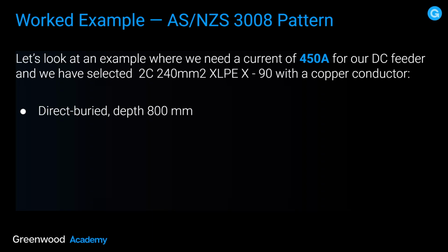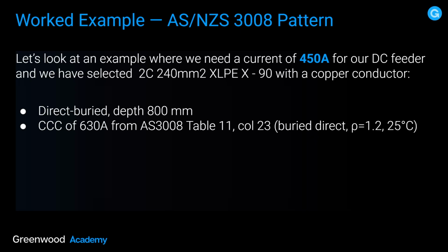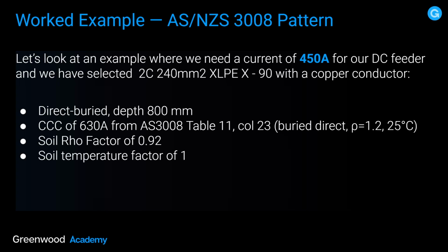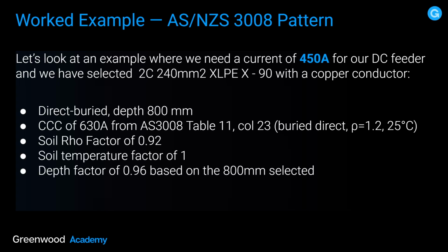So we've determined on this particular case study solar farm that we'll need 450 amps, and the cable we've gone to is a 240mm squared XLPE X90. Let's see what it looks like from a current carrying capacity. We're going to direct bury it at a depth of 800mm. Now, the CCC of 630 amps, this comes from AS3008, Table 11, Column 23, buried direct, and it assumes a thermal resistivity of 1.2 with a 25-degree soil temperature. We have a soil factor of 0.92, and we have a soil temperature factor of 1. And a depth factor of 0.96, and this is based on the 800mm selected.